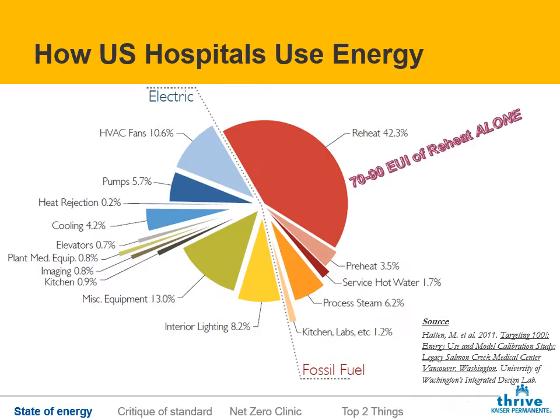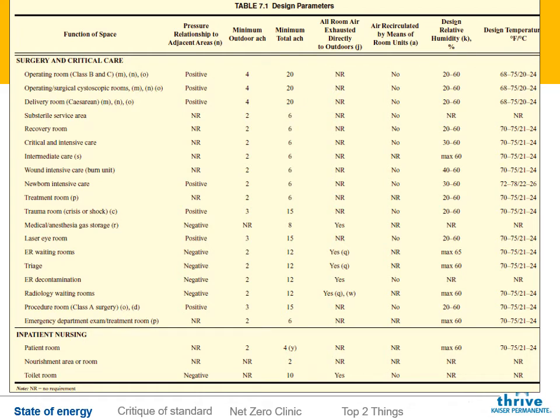So why do we have so much reheat? Well, this is why we have so much reheat. We design hospitals with a legacy HVAC method called air changes per hour. We have this table that tells us how many air changes to use for a lot of the spaces, most of the spaces in the hospital. And then this design method really sort of drives our energy use. These are the code minimums. Our design engineers tend to design above the code minimums because nobody wants to just do the code minimum. And then we tend to put these air changes into the spaces and run them 24/7. So it just sort of really drives our need for reheat.